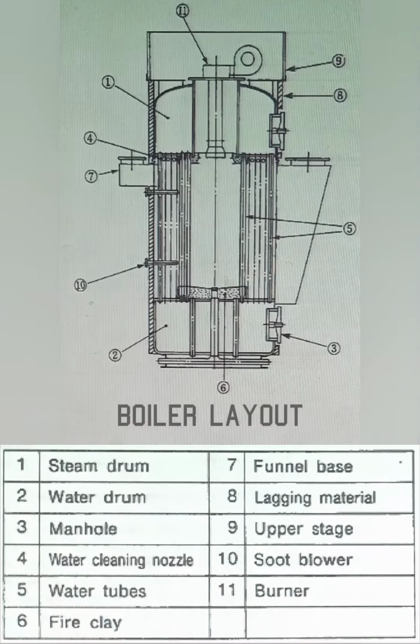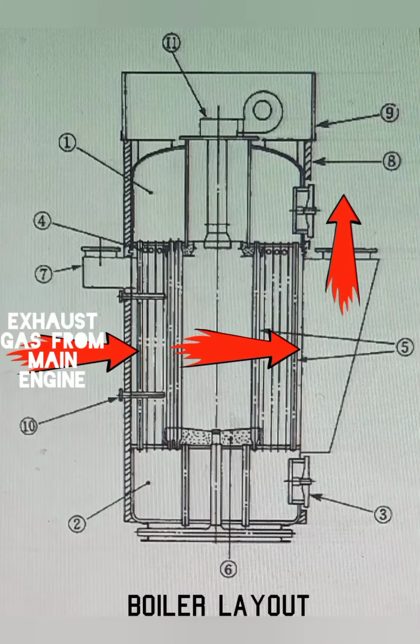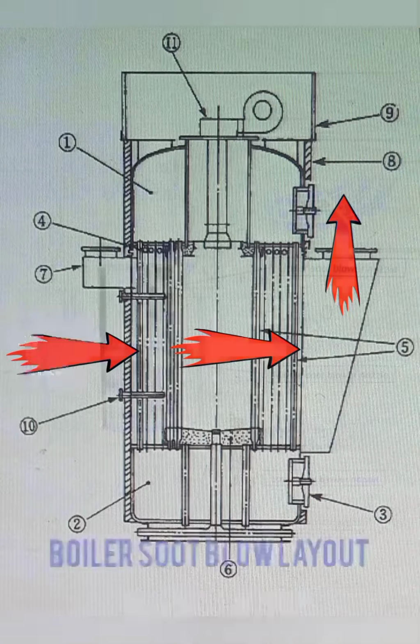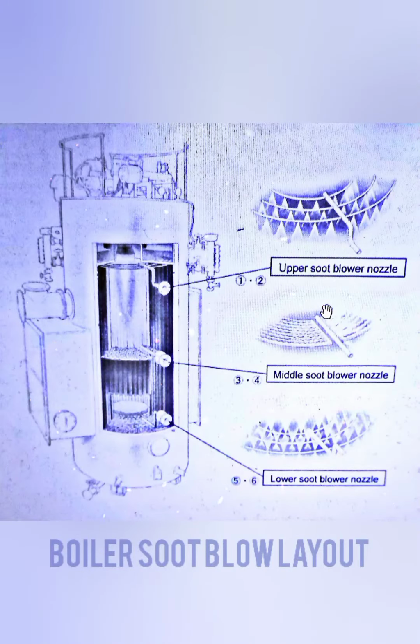A boiler economizer, or a flue gas heat recovery, is a heat exchanger installed on the stack of the boiler. The boiler economizer utilizes the heat from the exhaust gas of the main engine to raise the water temperature in the boiler to produce steam. In order to maintain the performance of our boiler economizer, carry out soot blow to remove the soot that is deposited on the heat exchanger tubes of the boiler.